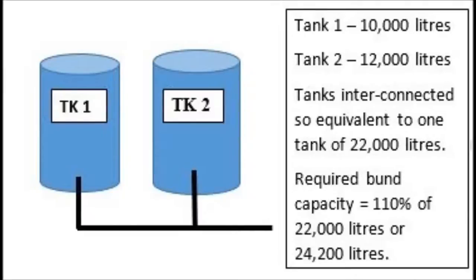A note of caution where two or more tanks are interconnected. If one of the tanks fails, the contents of the other interconnected tanks may also empty. If this is the case, the interconnected tanks should be treated as one large tank whose volume is the sum of the interconnected tanks.